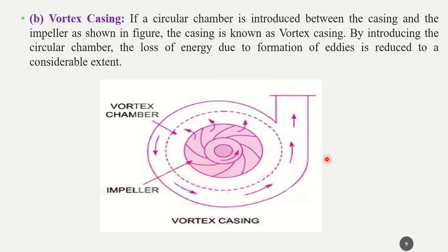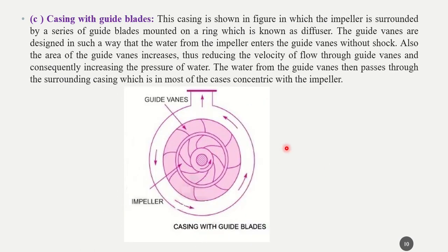When eddies form, pressure energy reduces, and since we require high pressure to deliver water to greater heights, eddies must be minimized. To address this, vortex casing is used. In vortex casing, a circular chamber is introduced between the casing and the impeller, as shown in the diagram — this circular chamber minimizes eddy formation.